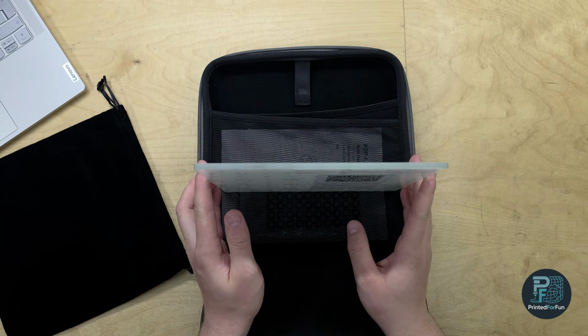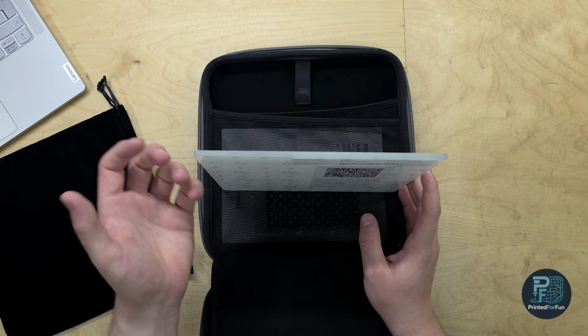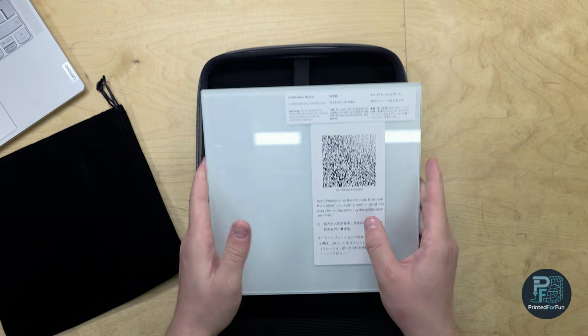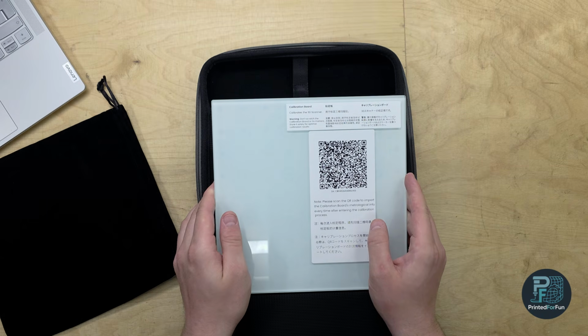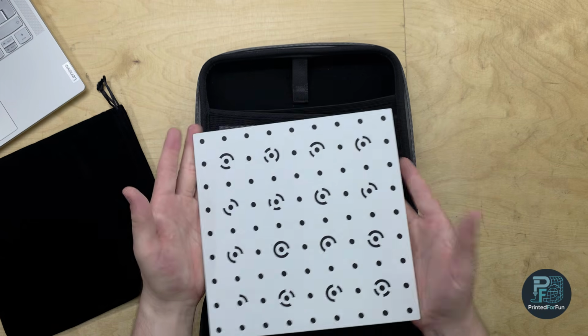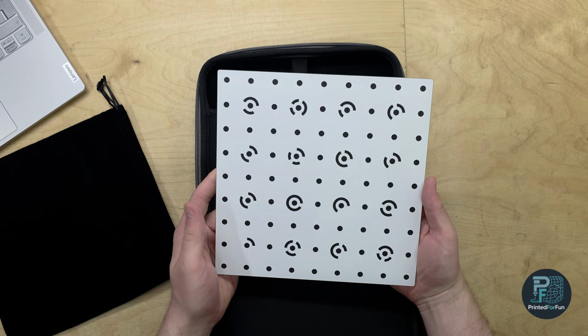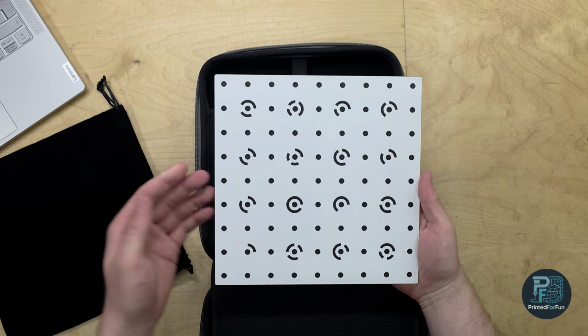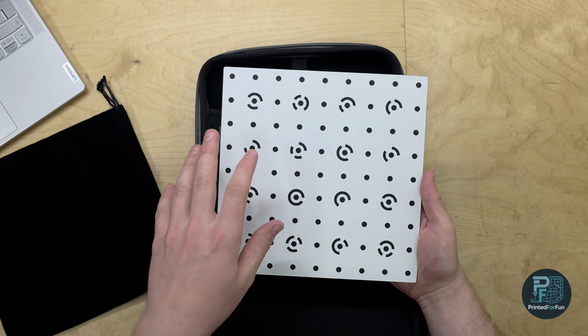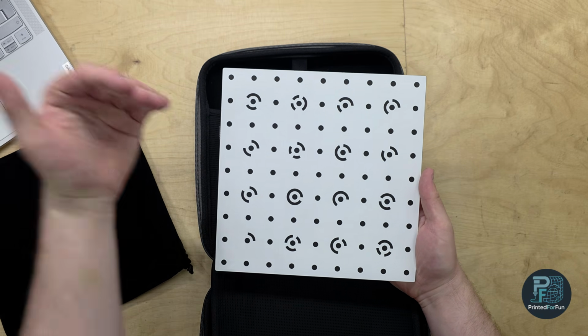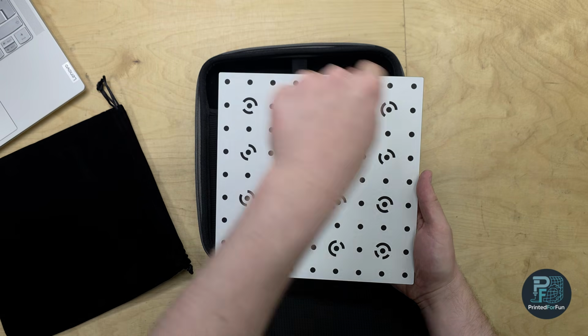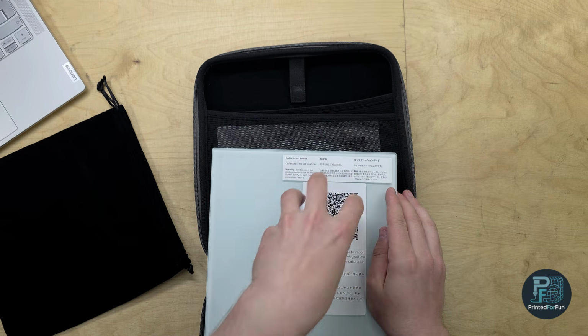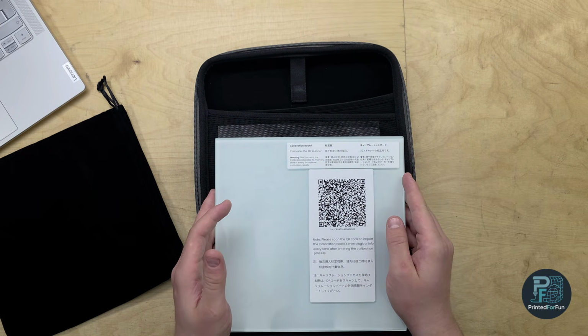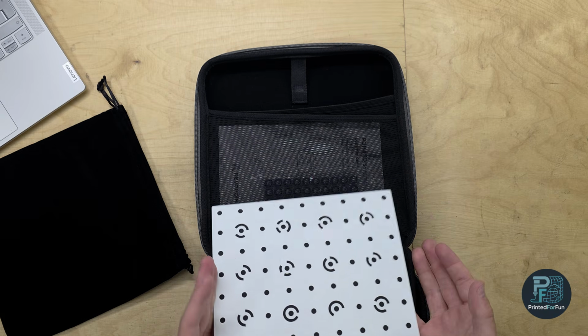I guess it's some sort of silicate glass that is quite accurate across the temperature range. On the back side, we have a sticker with the calibration code. So basically, what they do is they manufacture this board in their factory. And then there's always a bit of an error when printing these boards. But what you can do is you then measure the board and the dot spacing with a higher standard, and then you save it in a QR code. And then the scanner knows exactly how the point spacing should be on the board, and this data is then used for calibration.